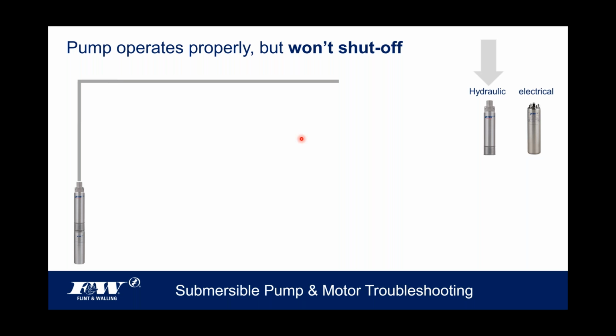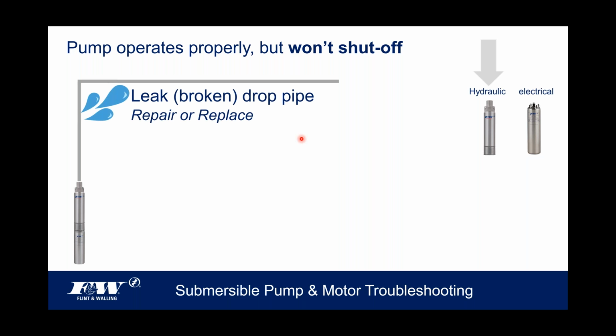Now this time, I'm going to move off that electrical side, which was the switch, and move back over to the hydraulic side, or at least the water, the movement of water, the pressurization of water. One of the things I might be looking at is the possibility that I've got a leak or a broken pipe. So when that pump's running, I'm losing a tremendous amount of water out of wherever that leak's at.